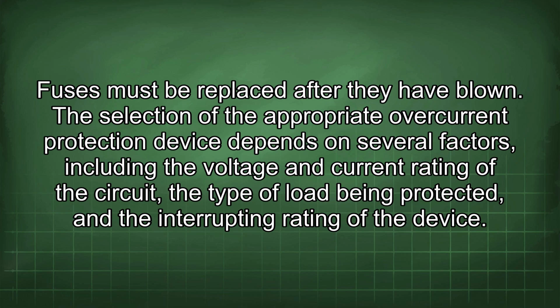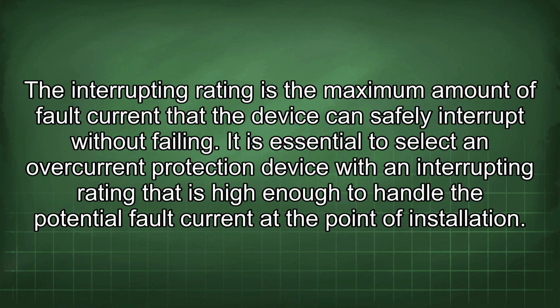The selection of the appropriate overcurrent protection device depends on several factors, including the voltage and current rating of the circuit, the type of load being protected, and the interrupting rating of the device. The interrupting rating is the maximum amount of fault current that the device can safely interrupt without failing. It is essential to select an overcurrent protection device with an interrupting rating that is high enough to handle the potential fault current at the point of installation.